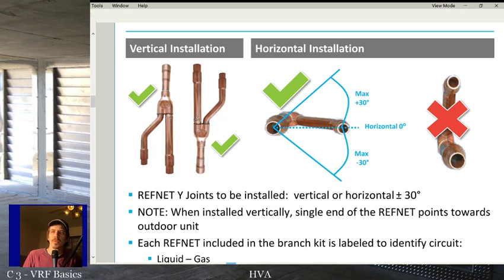The reason for that is, again, we're trying to split this refrigerant flow evenly, and there's going to be some liquid and some gas in the pipe pretty much all the time. We're never going to have a perfectly superheated vapor or perfectly subcooled liquid, especially on line sets this long when we're varying capacity. So if the liquid is flowing down and hits this portion where it splits, it should split relatively evenly between these two pipes. If these two lines are converging and it comes down, they should both enter this pipe kind of evenly. If the liquid is coming through and hits this evenly, it's going to split evenly.